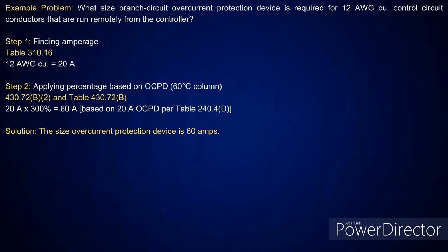Now, this is one where I'm running remote from the controller. Same exact conductors and everything, but look here, now I'm using table 310.16. It's good for 20 amps, and it's going to tell you to take it at 300%, which equals up to a 60 amp overcurrent protection device. And all of this is just a verification. The information's already in the table.